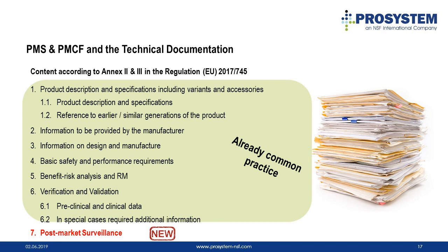It will not come as a shock to you that most of the requirements regarding the content of the technical documentation are not new when compared to the MDD. The most striking, however, is a new requirement that the PMS documentation must be part of the technical documentation.